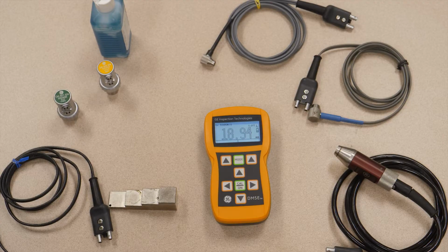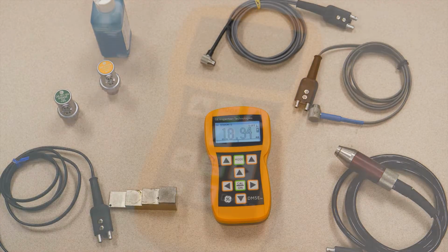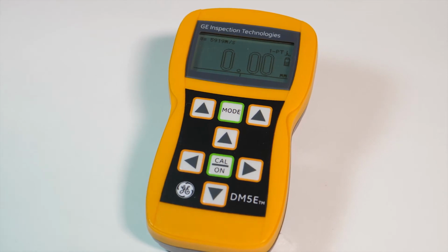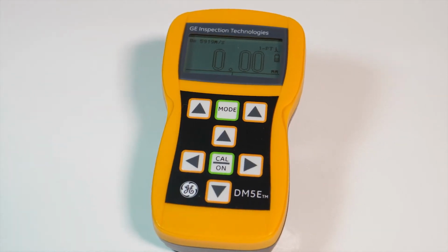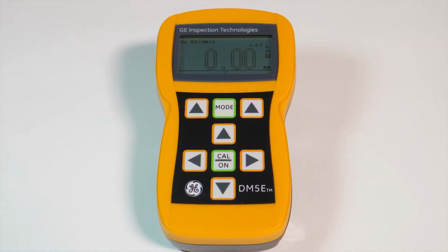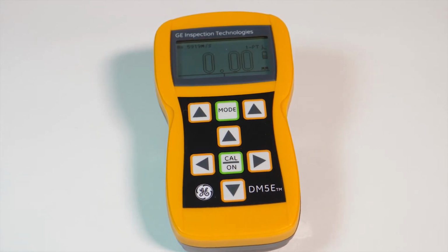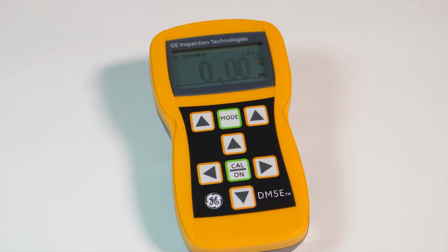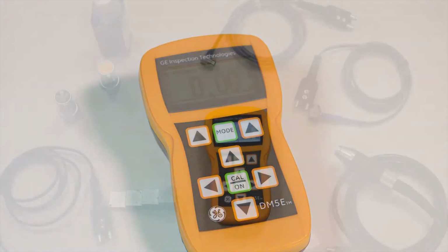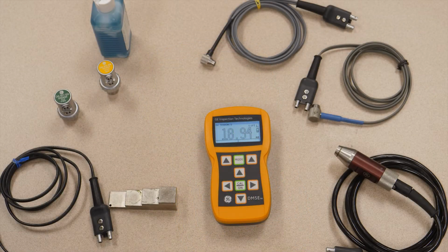Today I'd like to show you a little bit about the DM5E. It's our basic corrosion thickness gauge. Corrosion gauge meaning it's typically used for inspecting steel pipe or looking for corrosion in piping and tanks and other vessels. It has a precision of 3 decimal places of an inch, 2 decimal places of a millimeter, so 1/100th of a millimeter or 1/1000th of an inch.